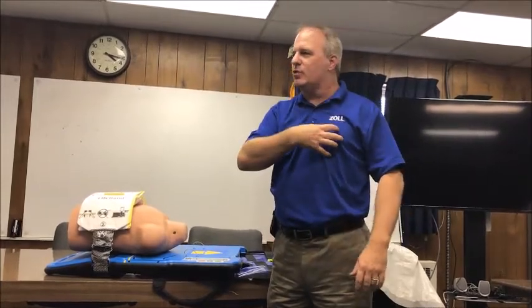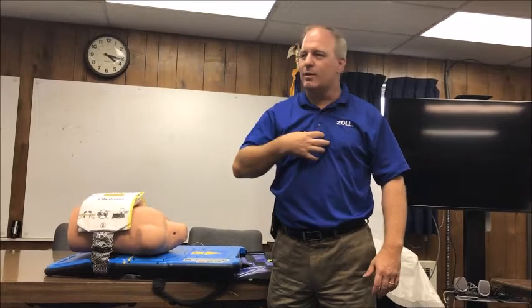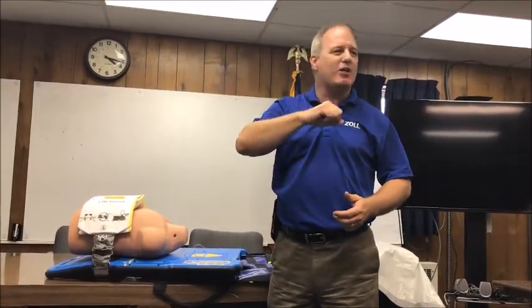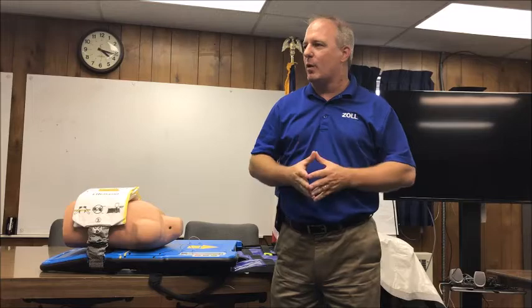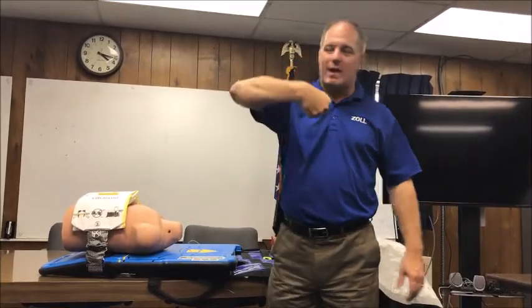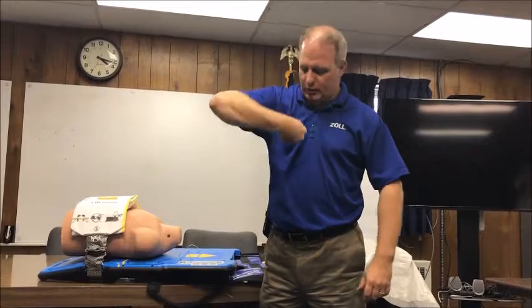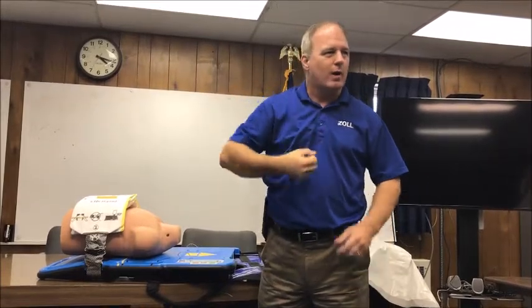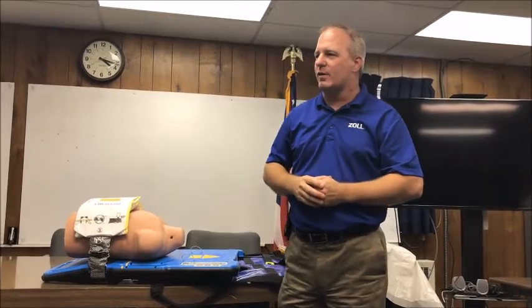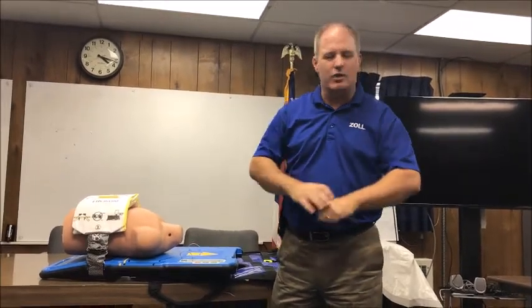So essentially you start to get pneumothorax on one side or the other. You'd turn your eyes briefly, you'd see the thing doing chest compressions on the patient's neck or on their belly, kind of overdramatic. But essentially the machine did not know what was going on. And it only did the anterior portion of the chest, only where the thumping portion would go. So sort of like manual CPR, we're only compressing a small portion of the chest and we're using an awful lot of strength and energy to do that.